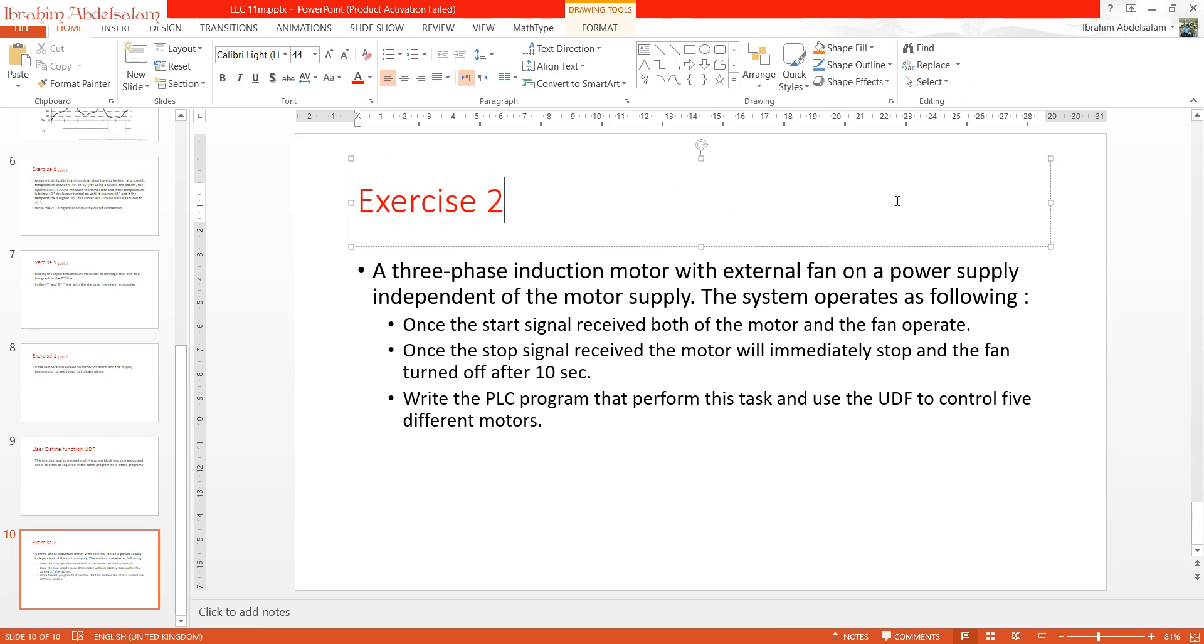Exercise 2: A three-phase induction motor with external fan on a power supply independent of the motor supply. The system operates as following: once the start signal is received, both the motor and fan operate. Once the stop signal is received, the motor will immediately stop and the fan will turn off after 10 seconds. Write the PLC program that performs this task and use the user-defined function to control five different motors.